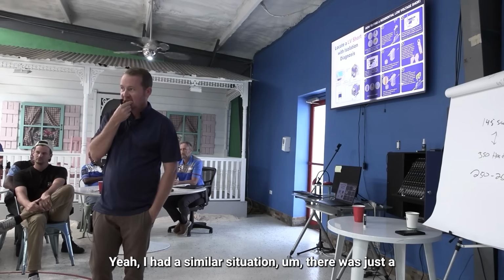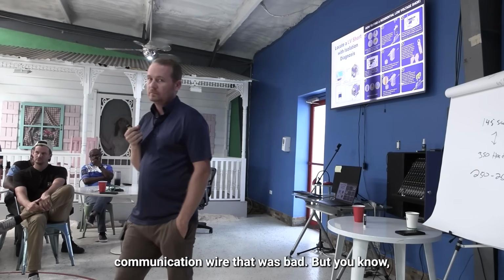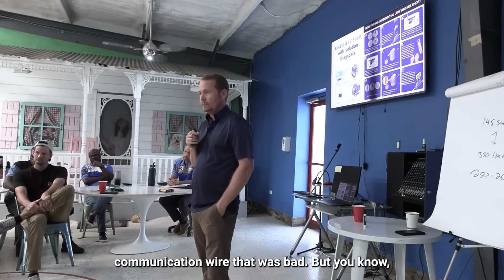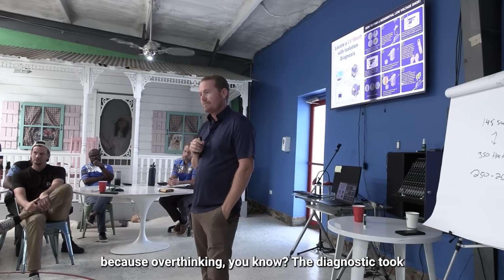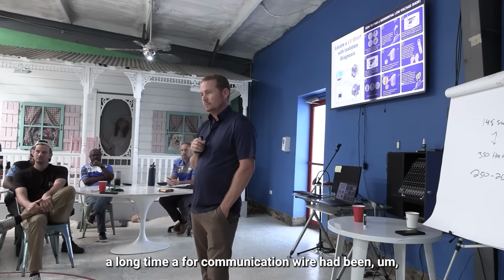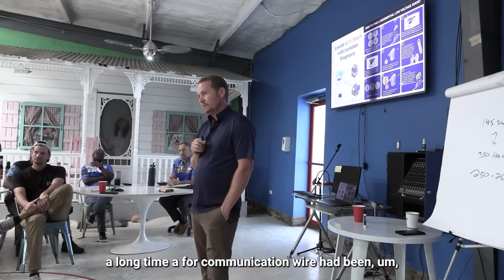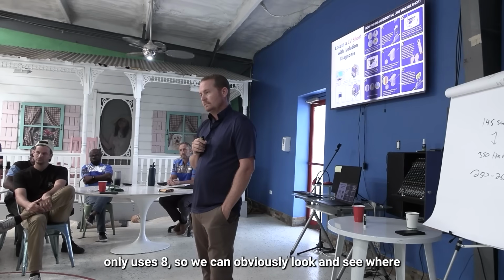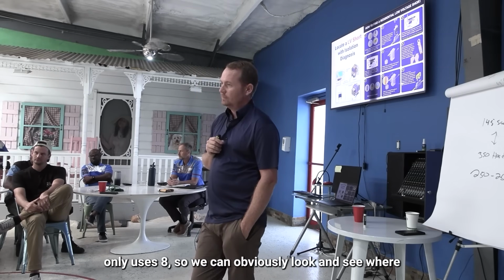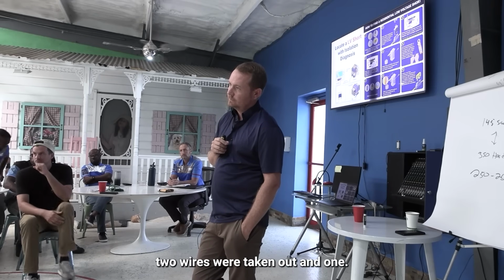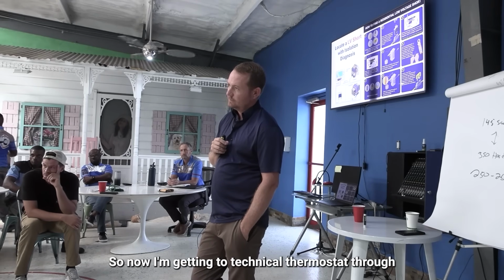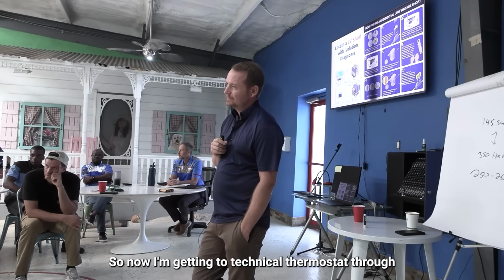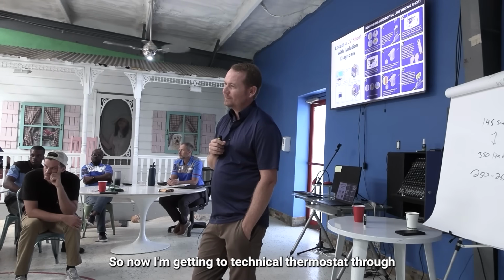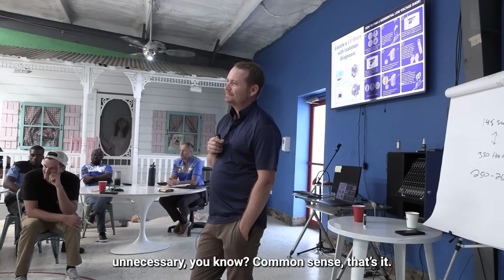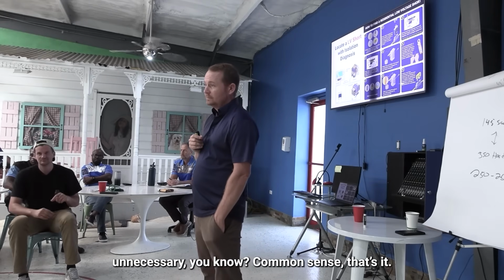I had a similar situation where it was just a bad communication wire. Because of overthinking the diagnostic, it took a long time to actually show me it was a 4-conductor communication wire. It turned out someone had only used the tools they could - you could see where 2 wires were used at one time, then taken out and 2 others used instead. I was getting too technical, going through the thermostat, looking at codes - all unnecessary. Just common sense.